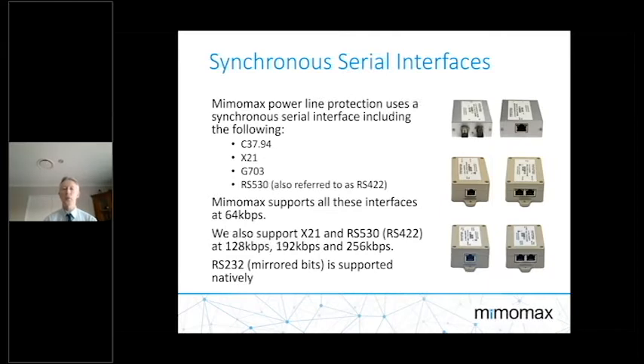Our interfaces: I mentioned earlier that we have the high-speed serial interface. Into that high-speed serial interface, into the radio, we have the option to connect a number of different devices and other interfaces. What we're showing here is the synchronous serial interfaces for power line protection, which would typically utilize C37.94 fiber, X21, G.703 or RS530 in terms of synchronous interfaces, also referred to as RS422 or RS485.